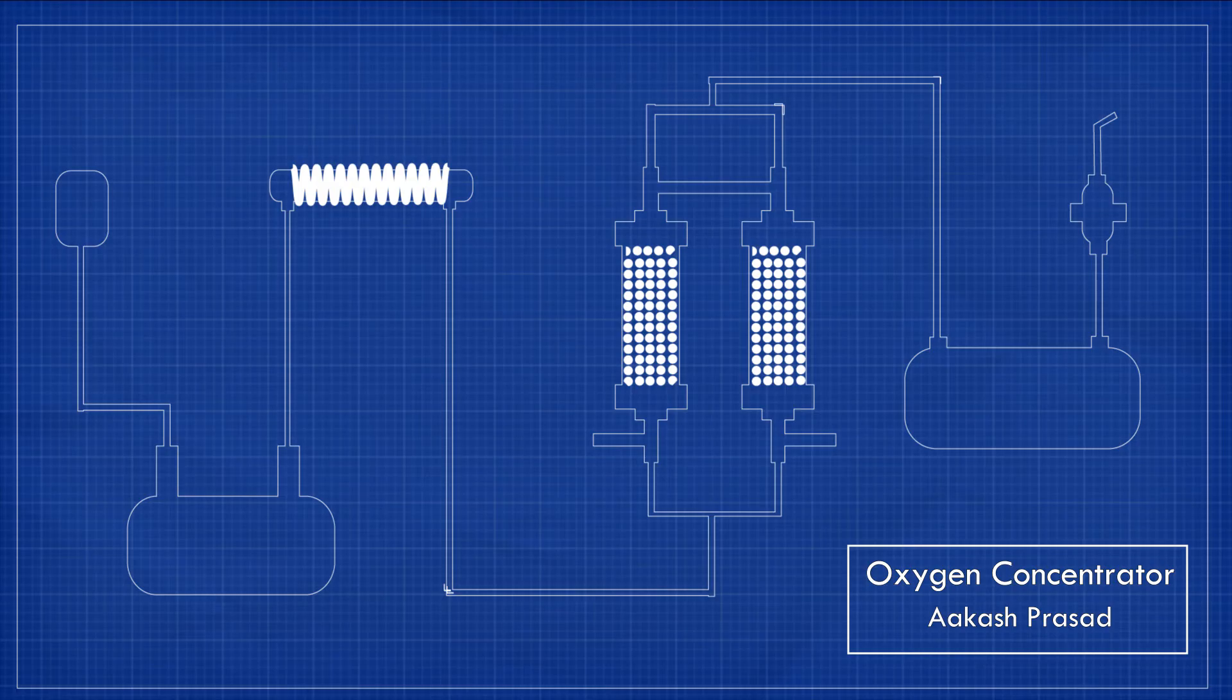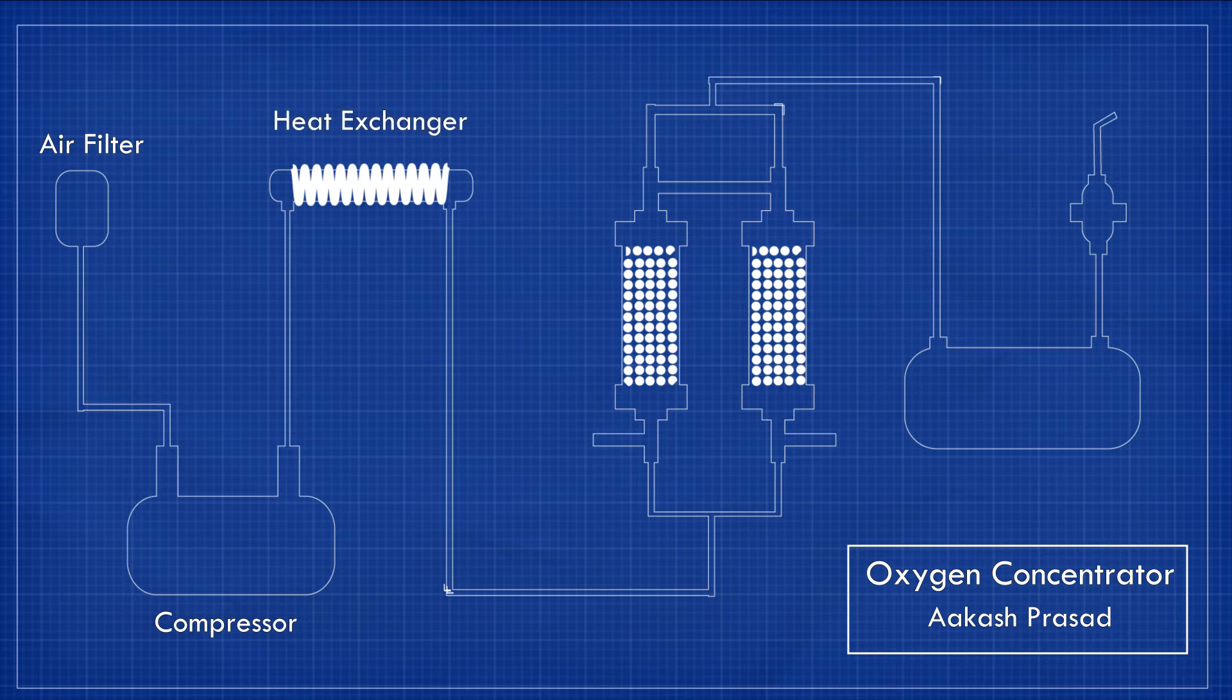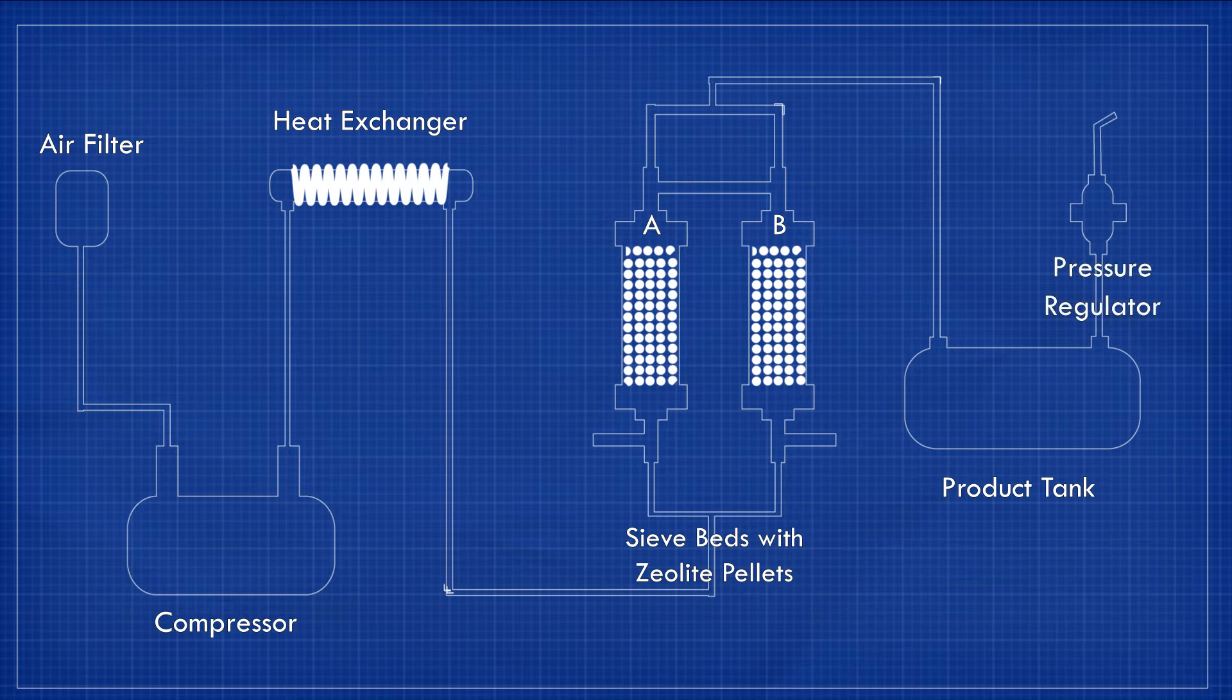The main components of a concentrator are air filter, compressor, heat exchanger, two zeolite sieve beds, product tank, and pressure regulator.